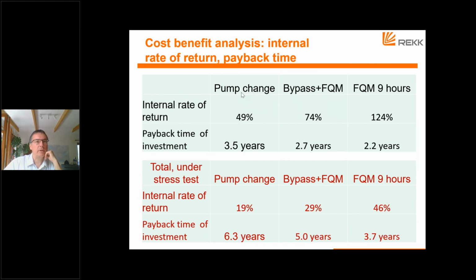Of course you can't do it every year buying new pumps, since it only makes sense once, but it has a very good investment profile with a payback time of only 3.5 years. With the other two investments the figures are even better, but only because the original investment cost is lower, and with this lower money you're still generating lots of energy savings. So you get very good return periods, just 2-3 years, and the original investment is already repaid. For the remaining 20-22 years, it keeps generating energy cost savings, which is why these figures are so good.